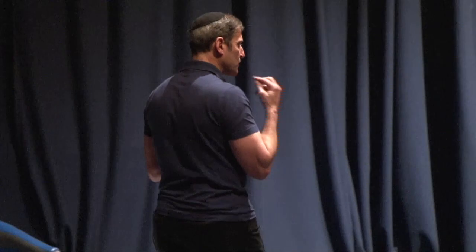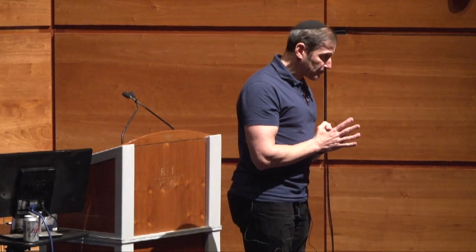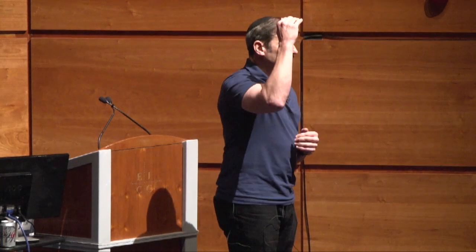One of the apps that we developed was developed in conjunction with the MR manufacturers. We got together with them and we said, you know those maps that you've generated? I'd like more detailed information about them. And if you give me that information, I would like to translate them, if you'd excuse me, into English, or at least into some kind of a language that the people that really need this data would understand more. Tables depicting a maximum spatial gradient of 840 Gauss per centimeter at a Z value of 134 centimeters from 0 have limited value to most of us, in my opinion.